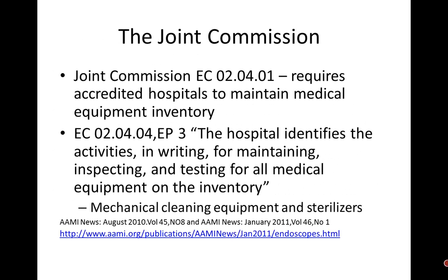So for those of you who might or might not be testing, or might not do it as frequently as you should, by these standards, that is something you should be doing. And we're going to address that with the standards and guidelines and talk about it. So again, mechanical cleaning equipment and sterilizers do fall under this category. As you'll notice on many of my slides, I will put the references on where I get the information from. So one of the references that I'm using today is AAMI, and the main reference is ST79.